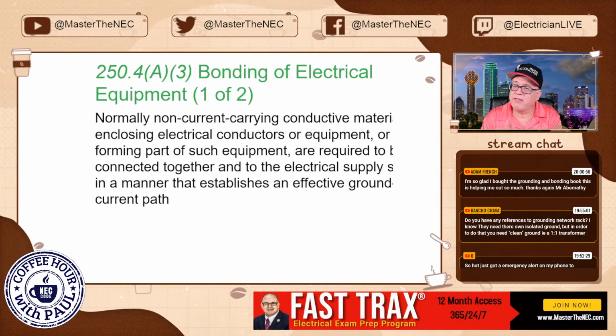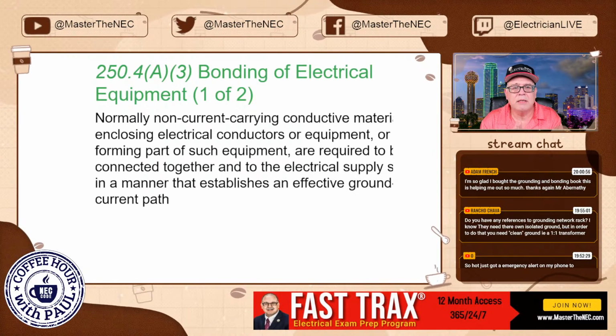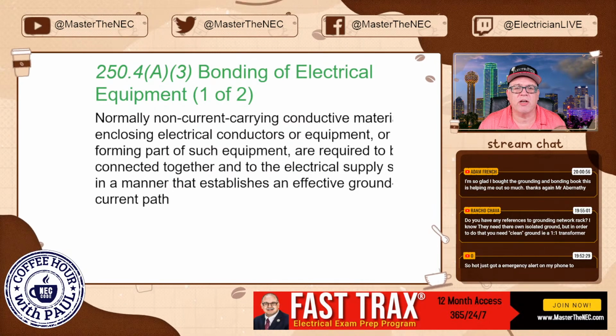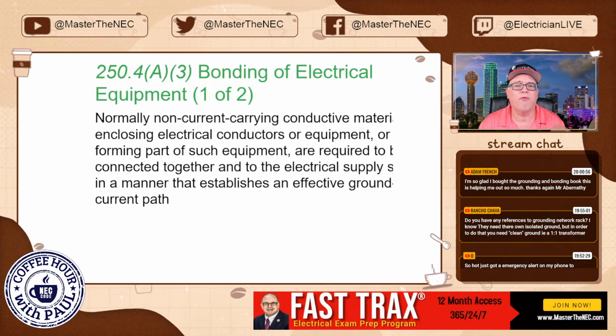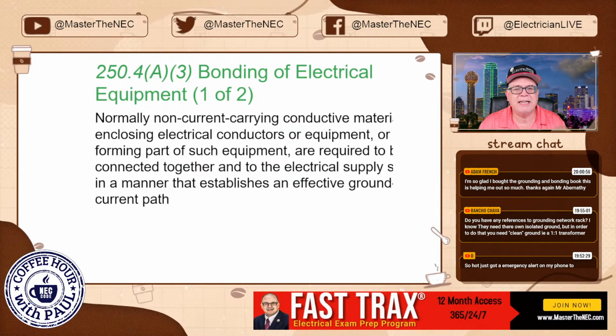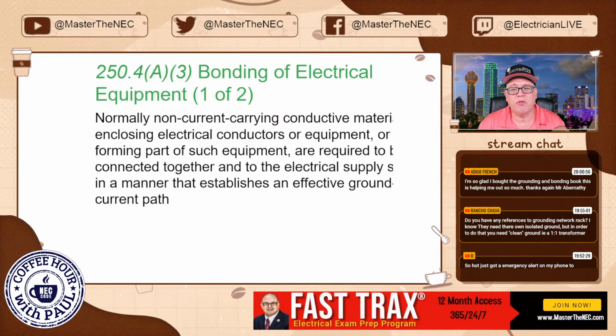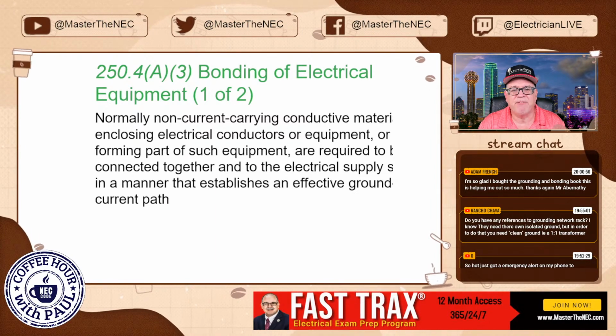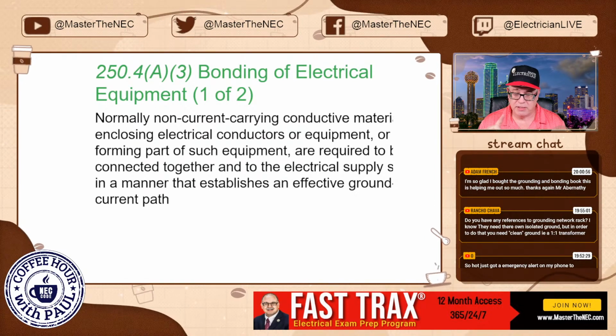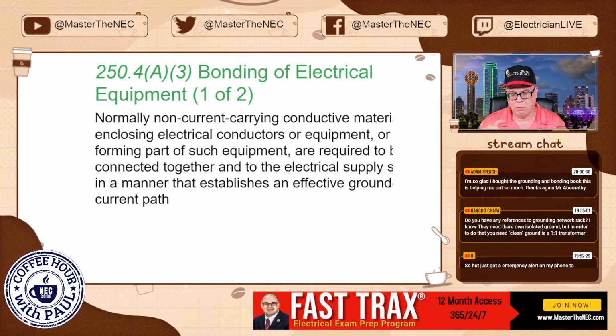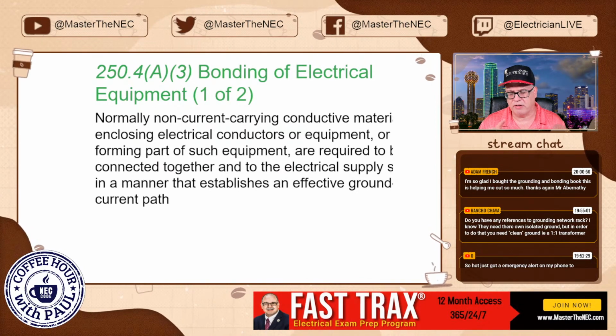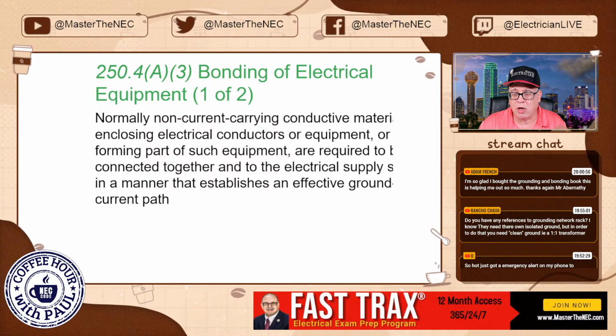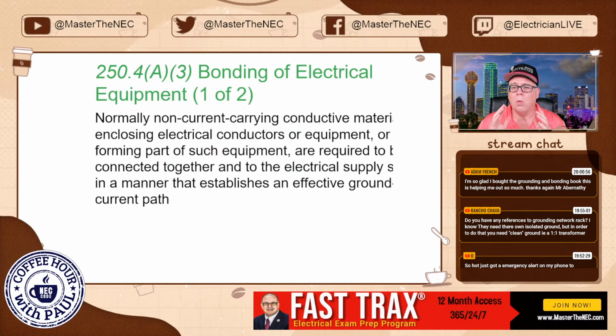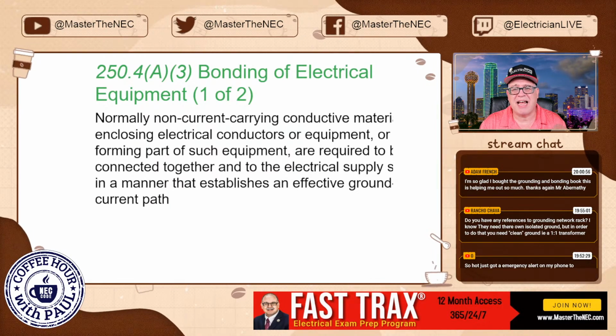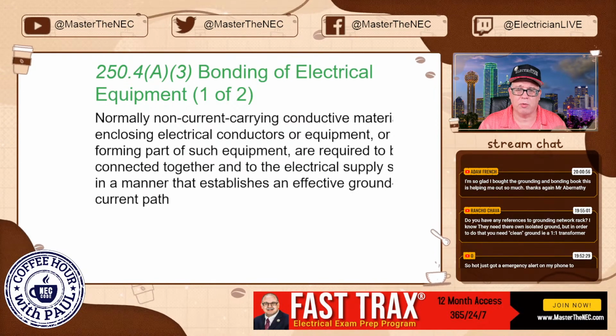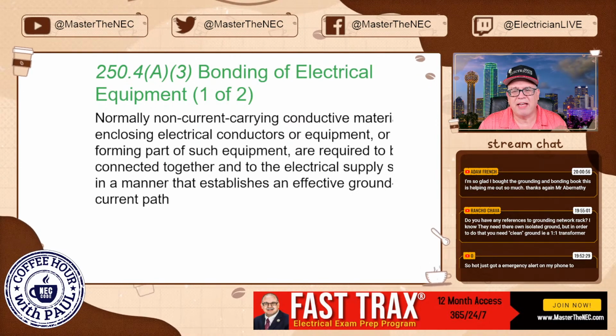250.4(A)(3), and I encourage you to follow along because I am paraphrasing. Normally non-current-carrying conductive materials enclosing electrical conductors or equipment, or forming parts of such equipment, are required to be connected together and to the electrical supply source in a manner that establishes an effective ground fault current path. So couplings, whether compression or set screw, connectors connecting to enclosures, lock nuts, whatever you're doing, we need to make sure of the whole concept of bonding electrical equipment: that we have that effective ground fault current path.